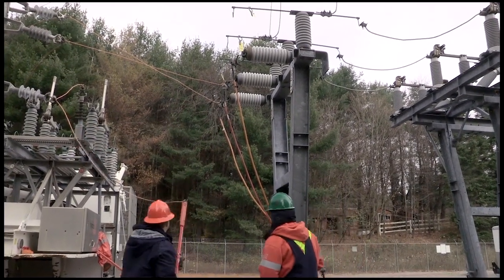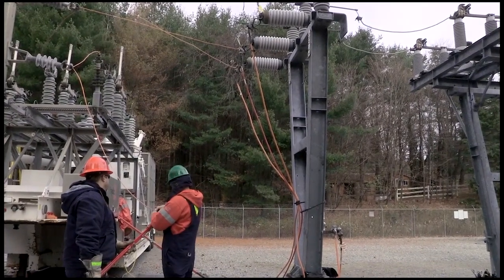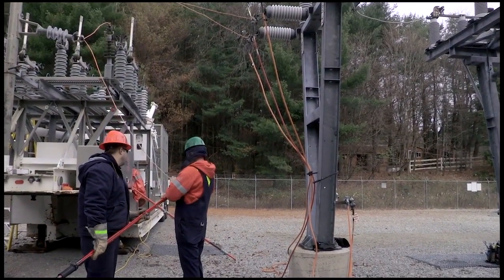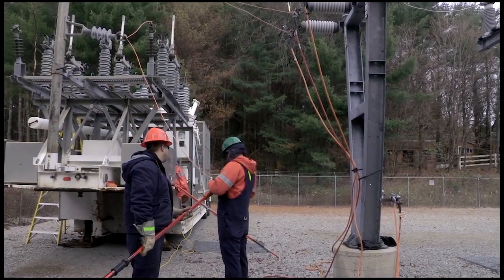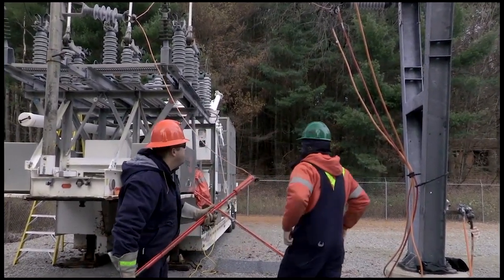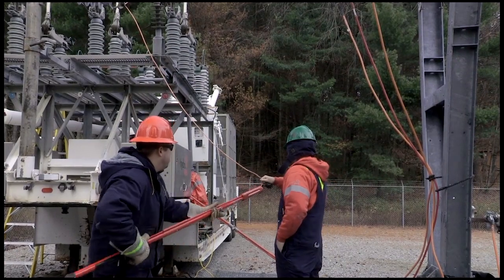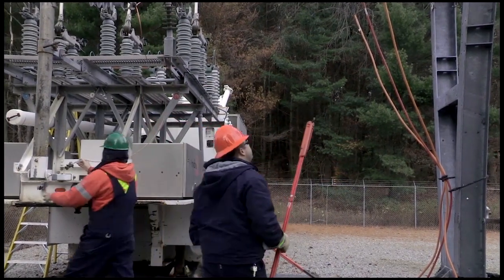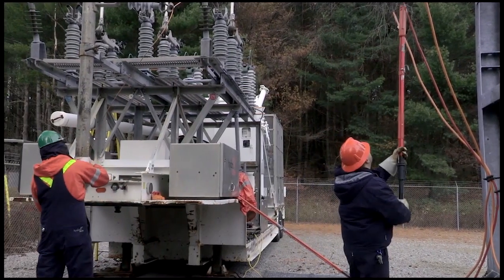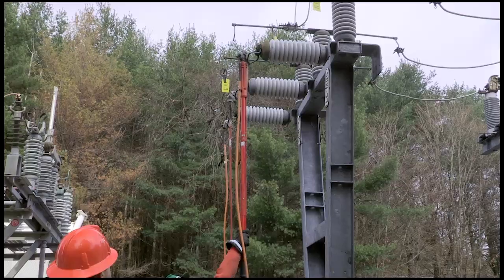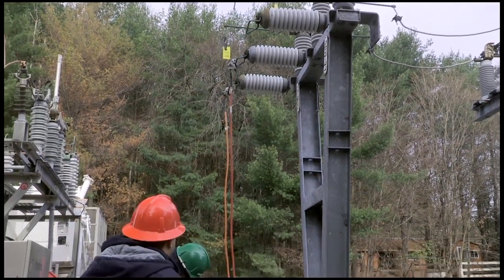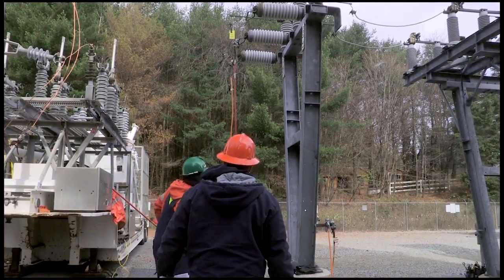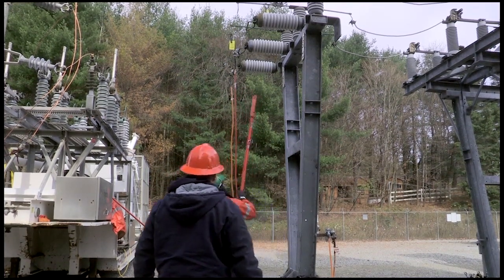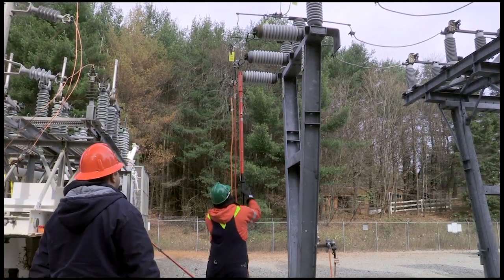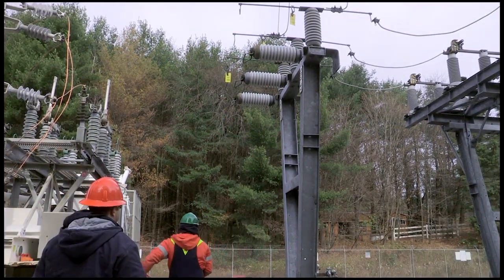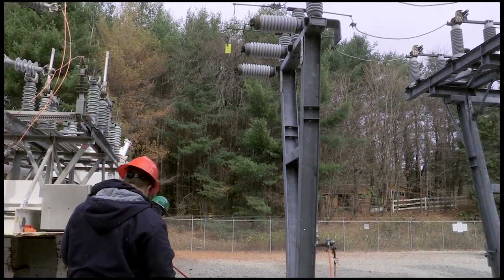Drop the leads down one at a time. As each one comes down, mark them with phase marking tape so that they don't get mixed up when you put them back up. Secure the loose ends to the MUS, someplace where the wind can't blow them into the live conductor. Once all three leads are down and secured, remove the three portable grounds and surrender the work permit on the primary side of the DS.